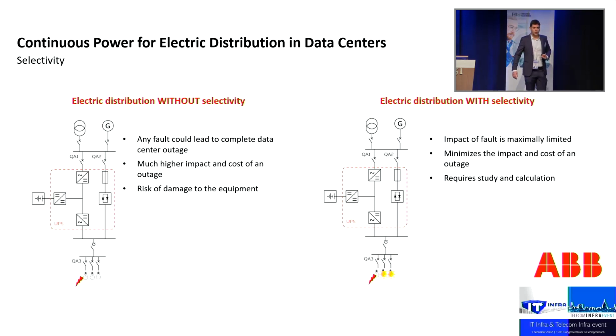So why is this important? On the left side, you see the system which doesn't have the selectivity. So in case I have a fault downstream of the UPS on one of the branches, one of my protection devices upstream will trip, maybe, and I will mention afterwards, the fuse inside of the UPS or even the upstream breakers.